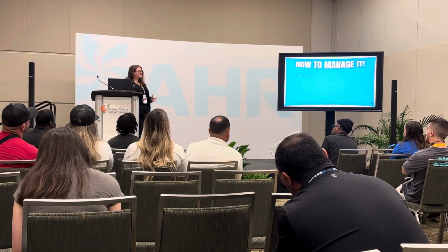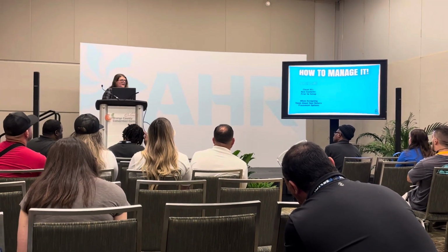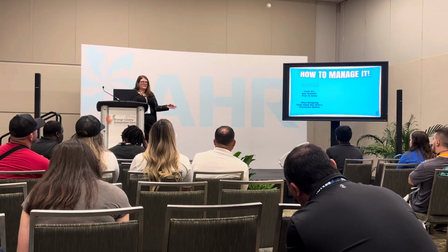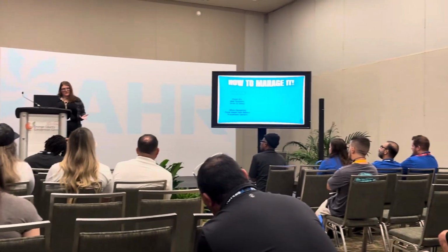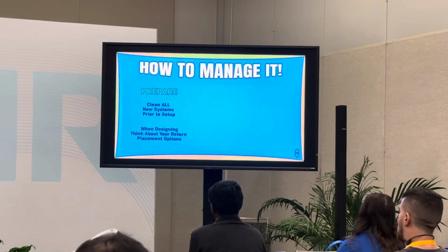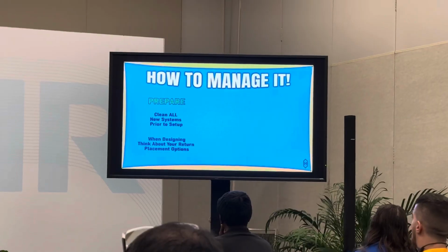So based off of everything, the research that we've done over the past 3 years, I highly, highly recommend that a brand new aluminum system that you get in, you need to clean it. I would really try to not put water on the system. We do make a cleaner that's solvent based, and it pretty much cleans it, it's self-rinsing. Now, if you gotta, you gotta, but I definitely think that you need to clean your systems before you even set them up.